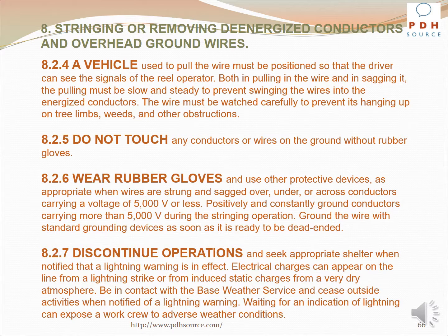Positively and constantly ground conductors carrying more than 5,000 volts during the stringing operation. Ground the wire with standard grounding devices as soon as it is ready to be dead-ended. Discontinue operations and seek appropriate shelter when notified that a lightning warning is in effect.